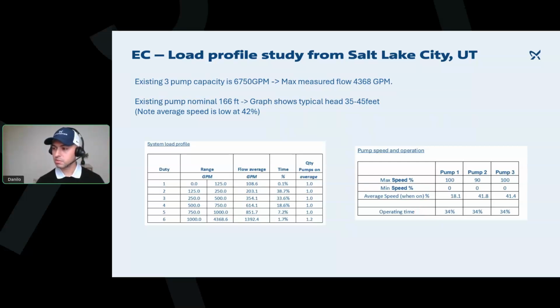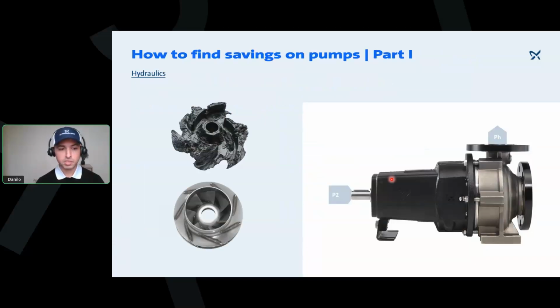Besides, now we spoke about efficiency, right? How to select the pump. And now we're talking about load profile. So next, I want to talk to you guys about the hydraulics, right? How do you identify hydraulics? How do we find savings? Hydraulics is another very big, important part of it. Pumps are designed, I want to say, at least the Grundfos pumps are designed to run for 25 years, and it will depend very much on how they operate, how they're maintained. But we know our customers expect to run them for much longer than that.